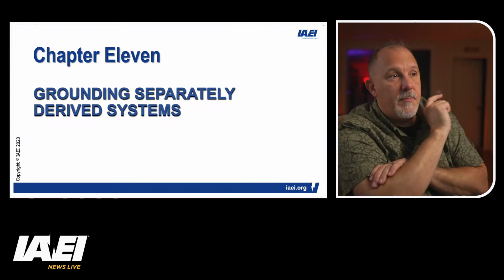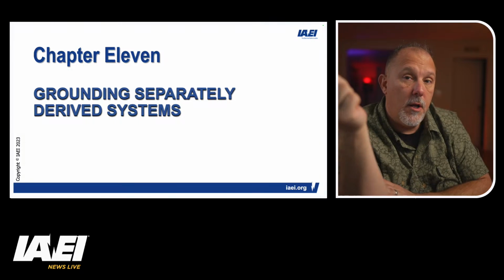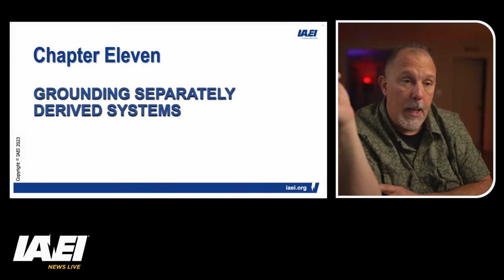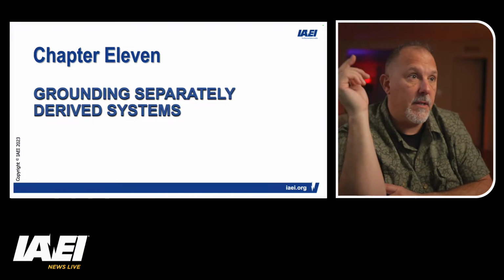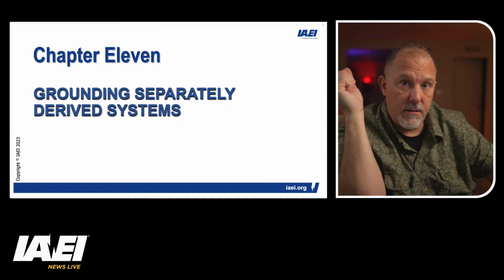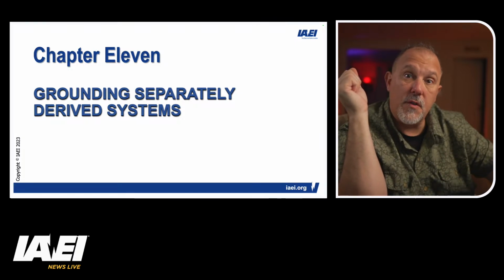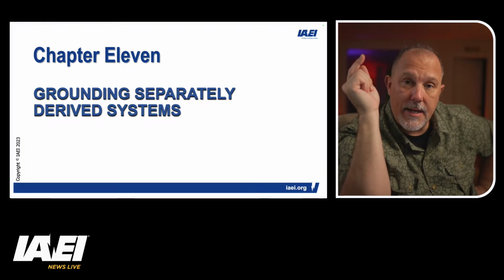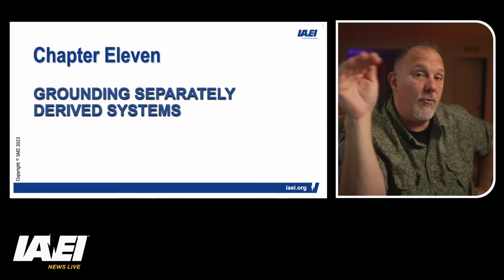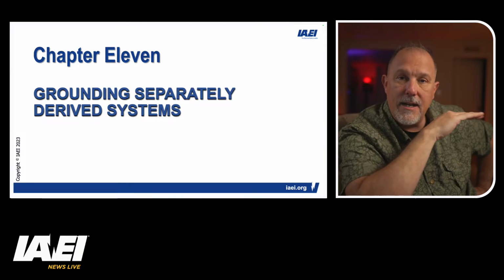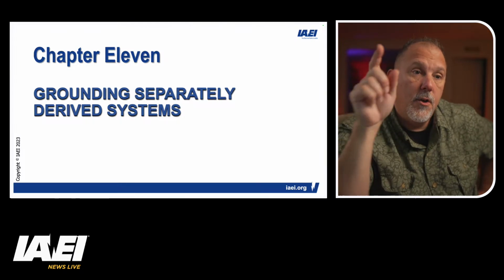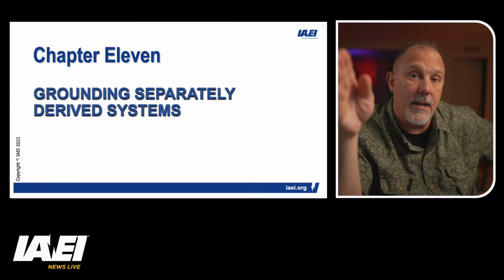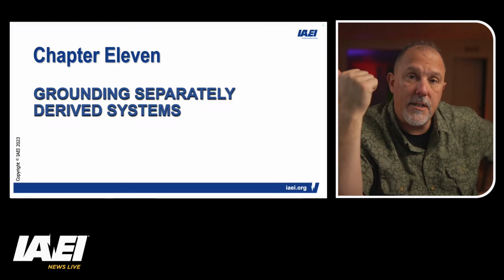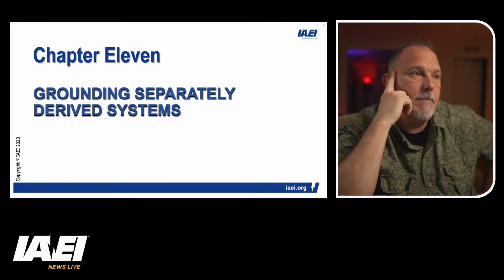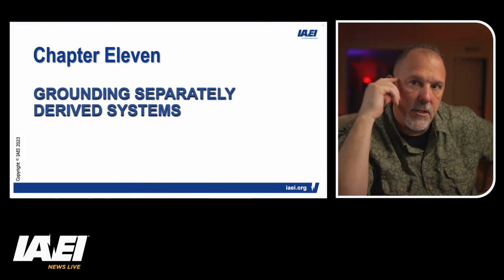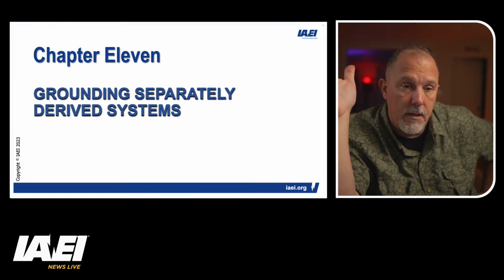All right. An electrical power supply output other than a service. So we know a separately derived system is not a service. Period. When we identify a separately derived system, it's not a service. We have a definition for what a service is, and we take care of that as part of Article 230, etc. So an electrical power supply output that is not a service, having no direct connections to circuit conductors of any other electrical source. We're not talking grounding and bonding. We're talking circuit conductors. That's your hot, your neutral, your grounded conductor, your hot conductors, three-phase systems, other than those established by grounding and bonding connections. So we're not talking about the grounding and bonding connections. We're going to bond everything together. That's not what we're talking about.